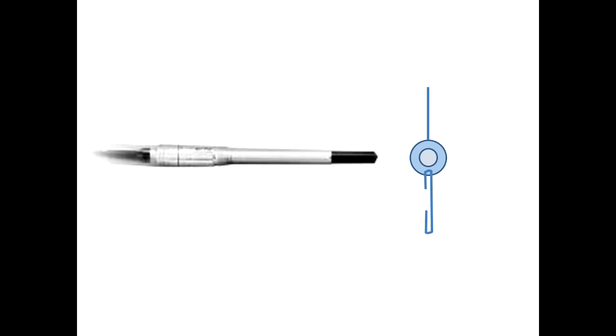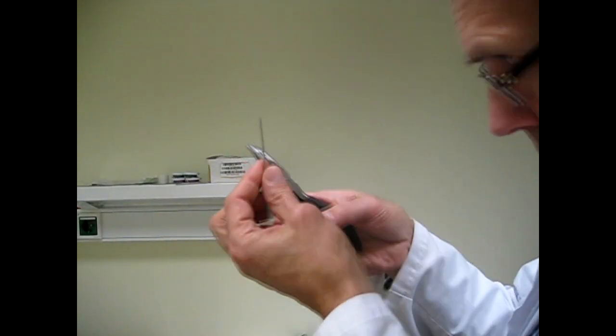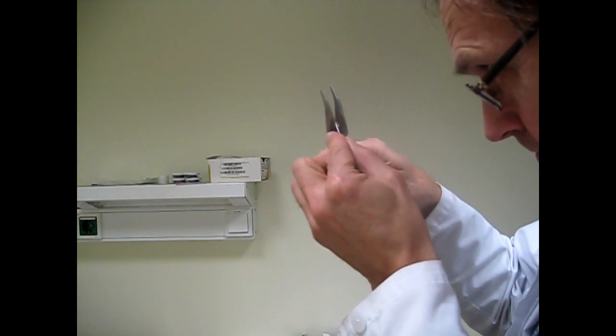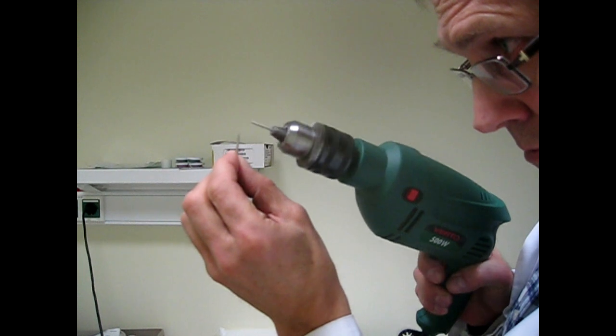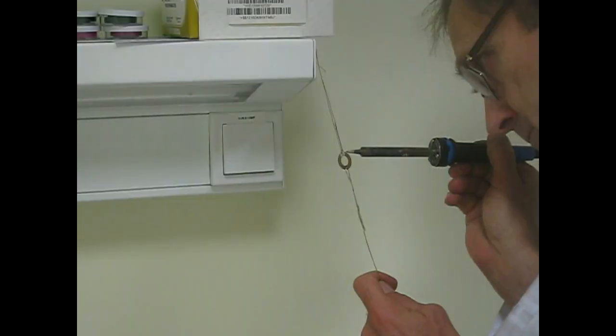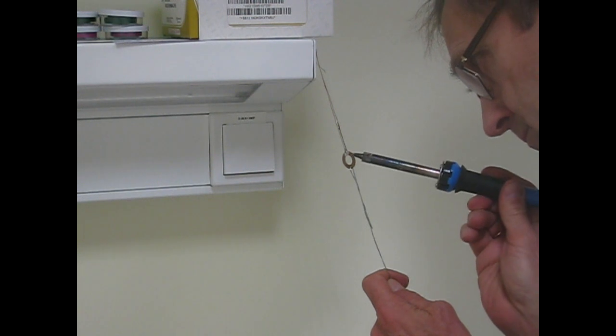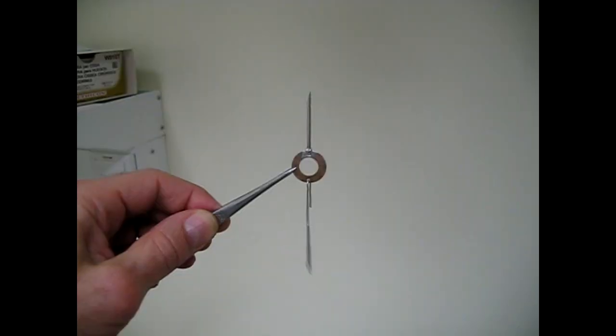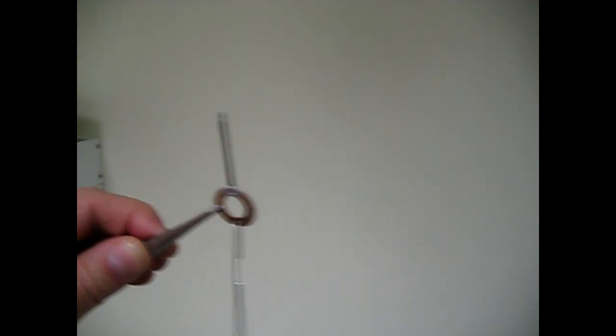We will start with the measurement of the length of the empty device, but before that, I'll show you shortly how to make this device using medical and improvised materials. I'll take a tool which we put on the ionization chamber and which consists of a thin washer, a vertical rod and a plumb wire. The 2 mm diameter needle I use as the rod of the empty device. I drilled some holes in the needle and washer to help me connect the washer with the rod by soldering. As a result, the rod and washer should be lined up.